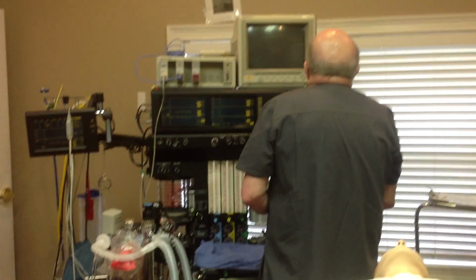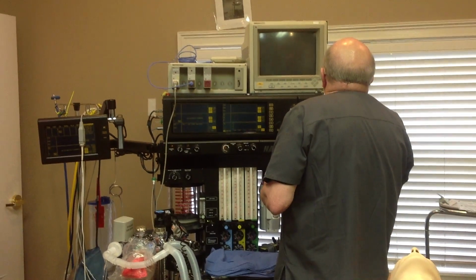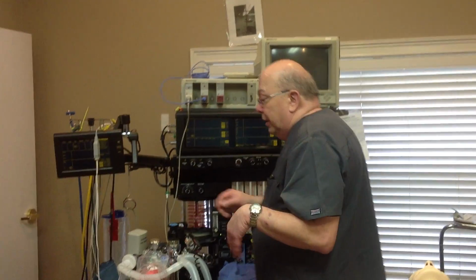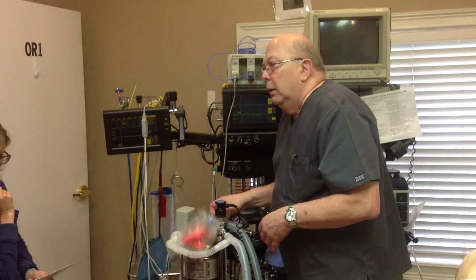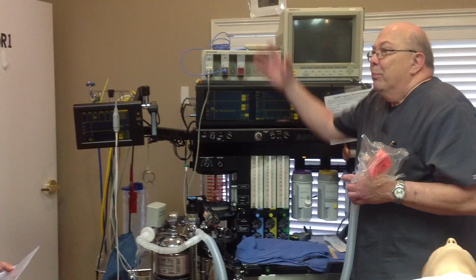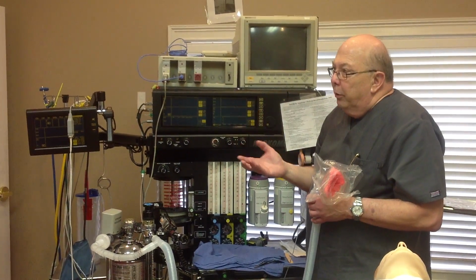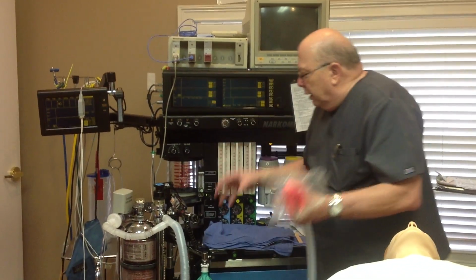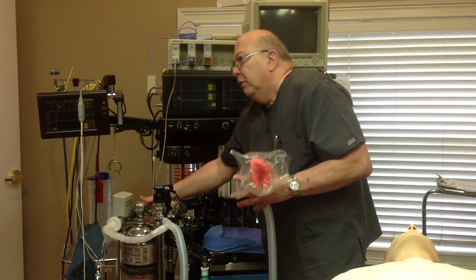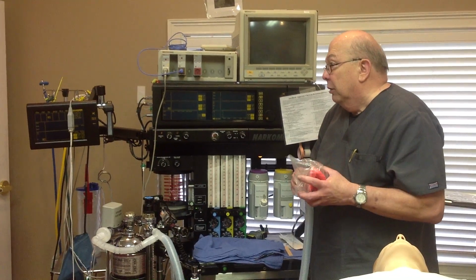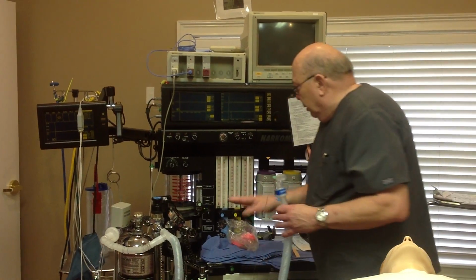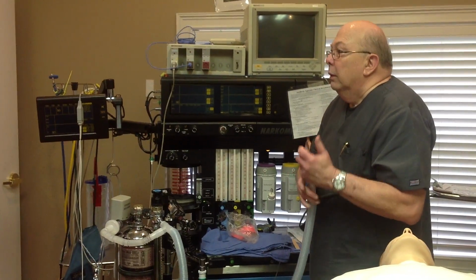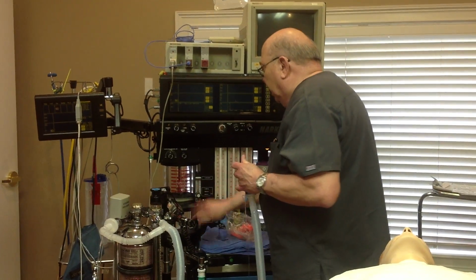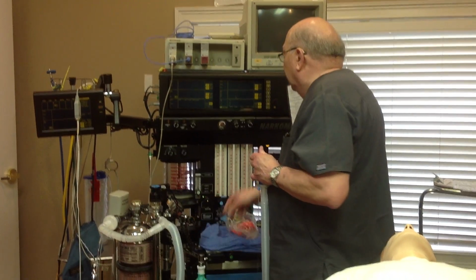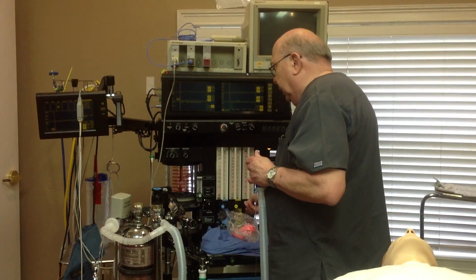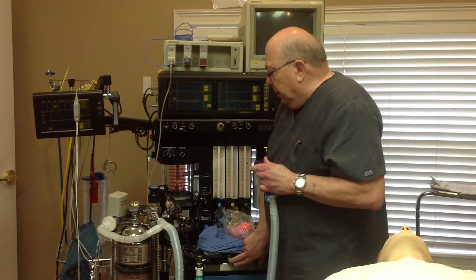Next step is number 11. Perform a high pressure leak test. The other one, now we're going to have the high pressure systems on, so we're going to do a higher pressure check. So now we're testing the internals of this breathing system, that there's no other leak that we have missed. So we're going to take our mask off. We're going to include the Y piece at this point in time. We're in bag mode. Have some oxygen flowing. And then I can inflate my bag here.